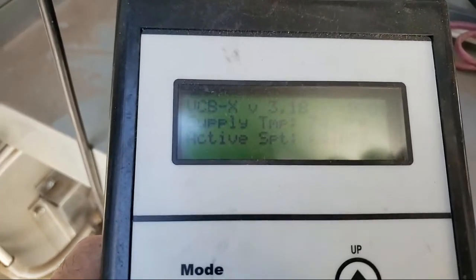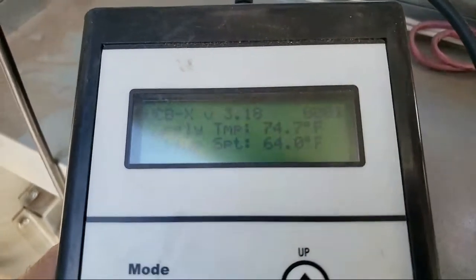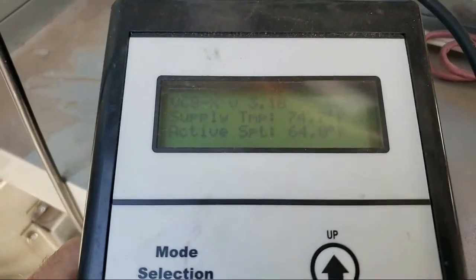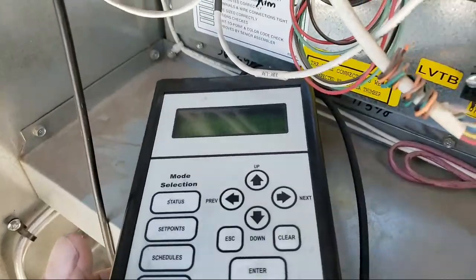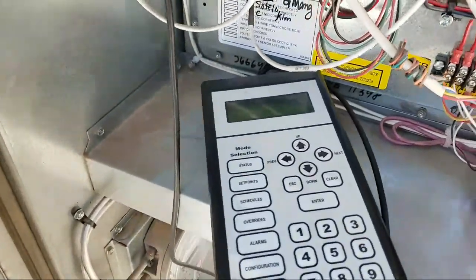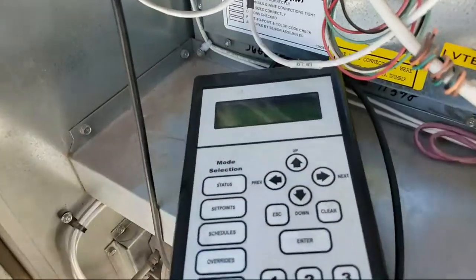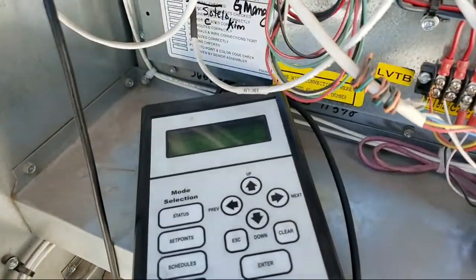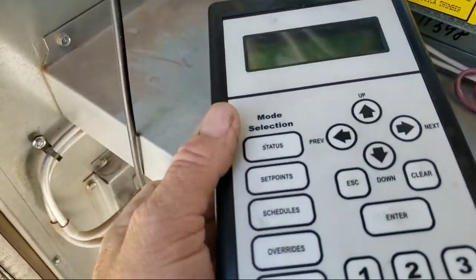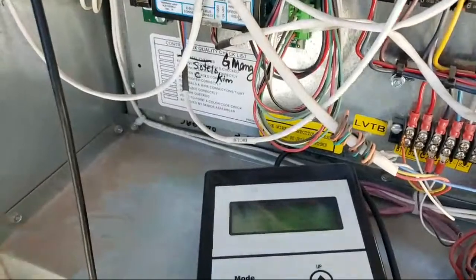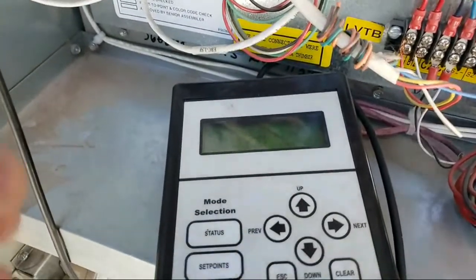Supply air is at 74 now, so you can tell it must be sucking in just a little bit of outside air, because the space is 68.5, and every time it's blowing the air back in, it's gaining 5.5 degrees. So that little slight fresh air opening, which is almost shut completely, must be bringing in something, plus all the ductwork and heat and stuff. It just sort of clicked, so I don't know if that was one of the changeover valves or something getting ready to start the compressor.